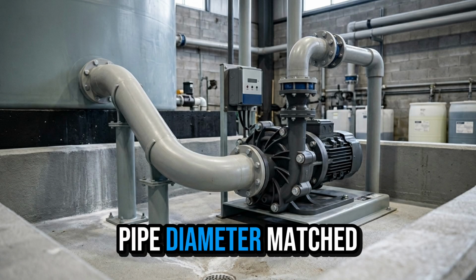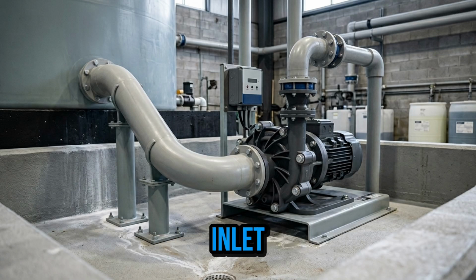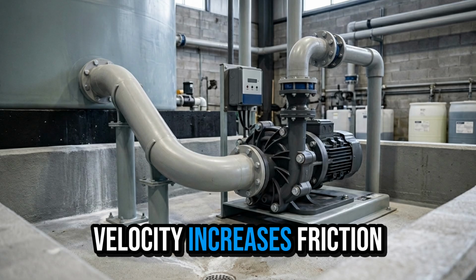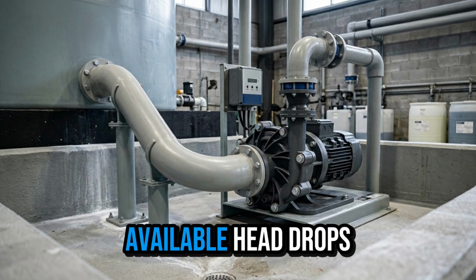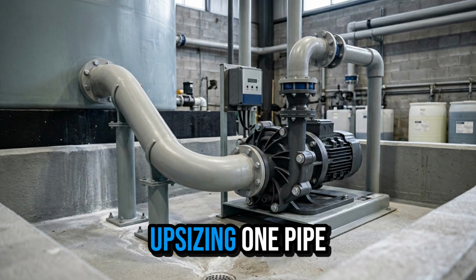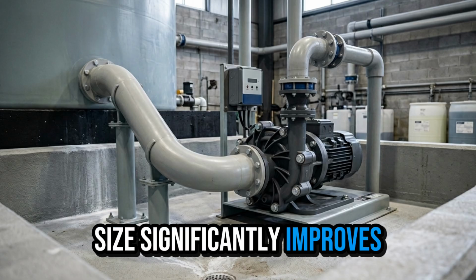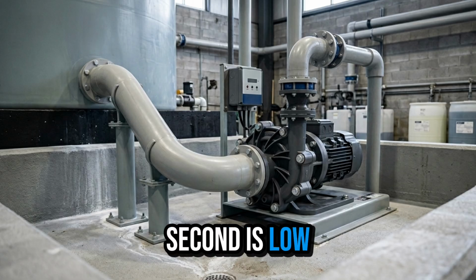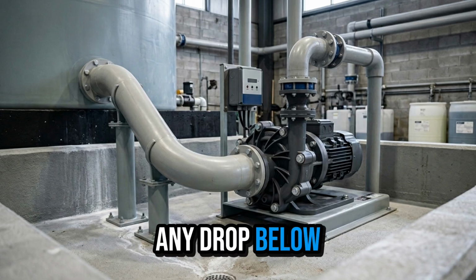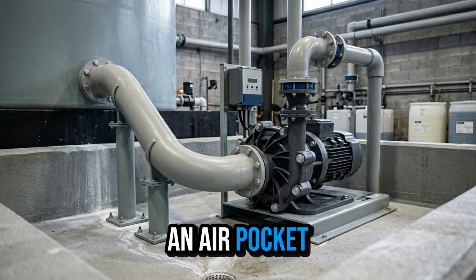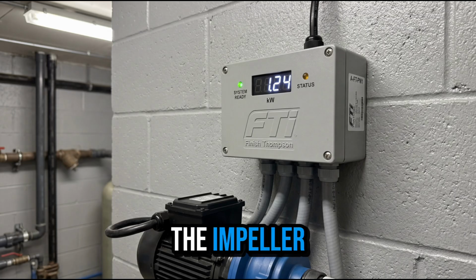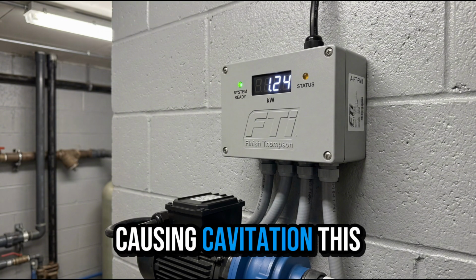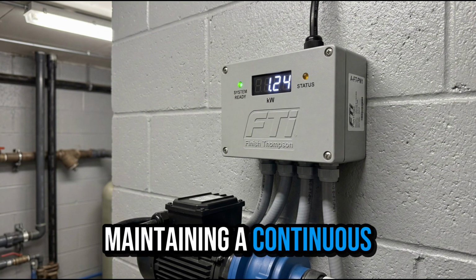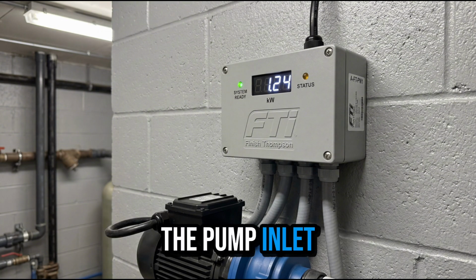First is suction pipe diameter matched to the pump inlet. Velocity increases, friction losses rise, and available head drops. Upsizing one pipe size significantly improves NPSHa. Second is low point traps. Any drop below pump centerline creates an air pocket. Each startup pulls that air through the impeller, causing cavitation. This is solved by maintaining a continuous upward slope to the pump inlet.